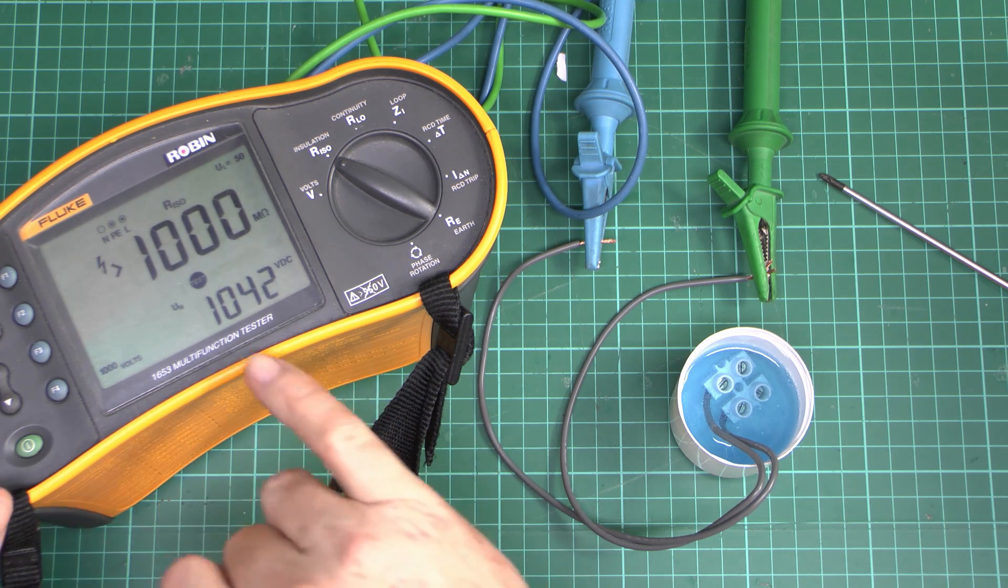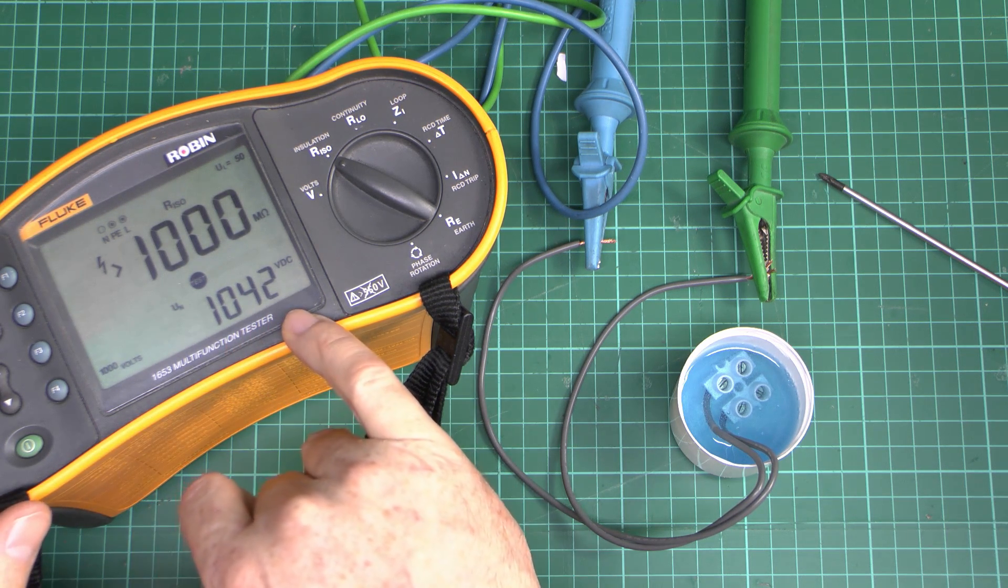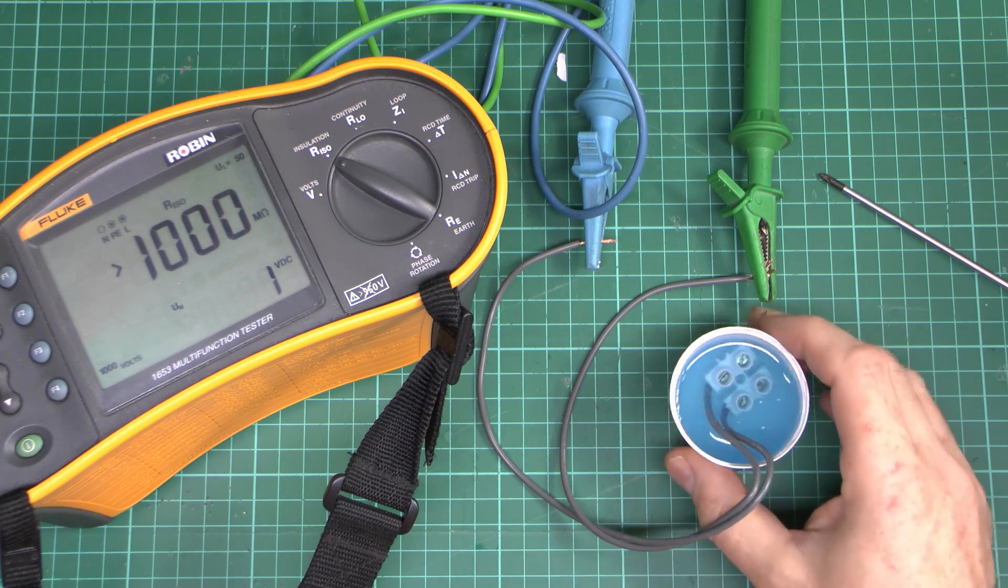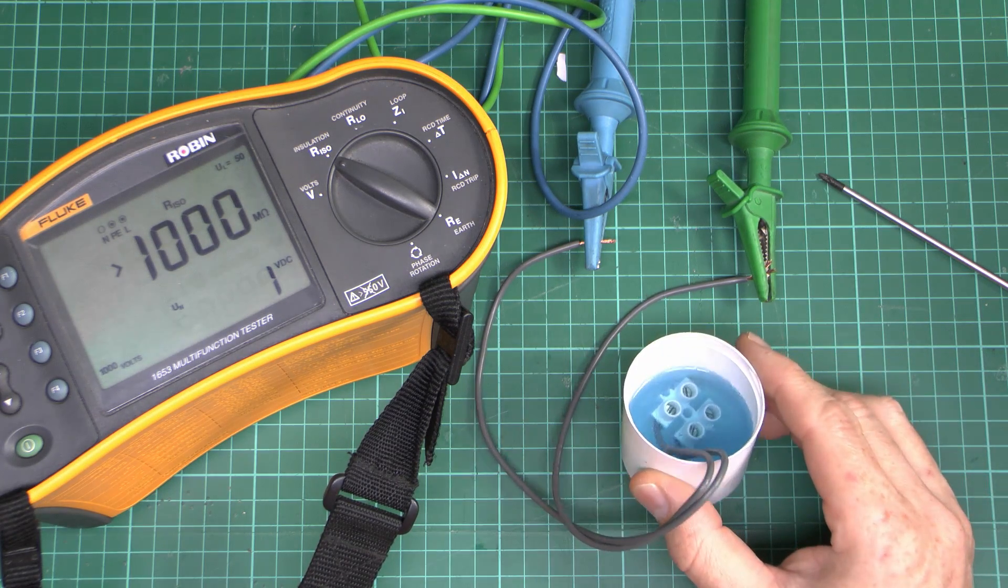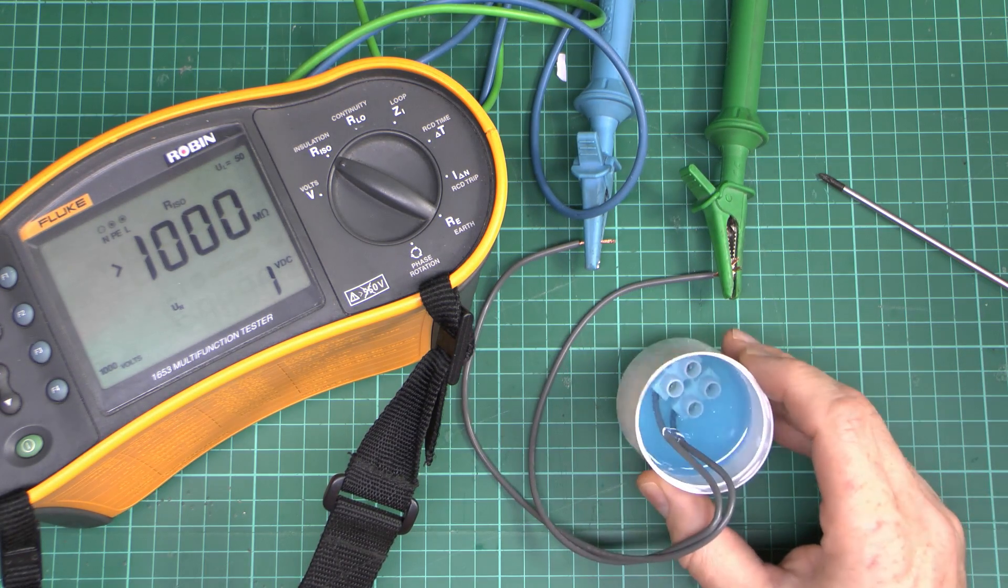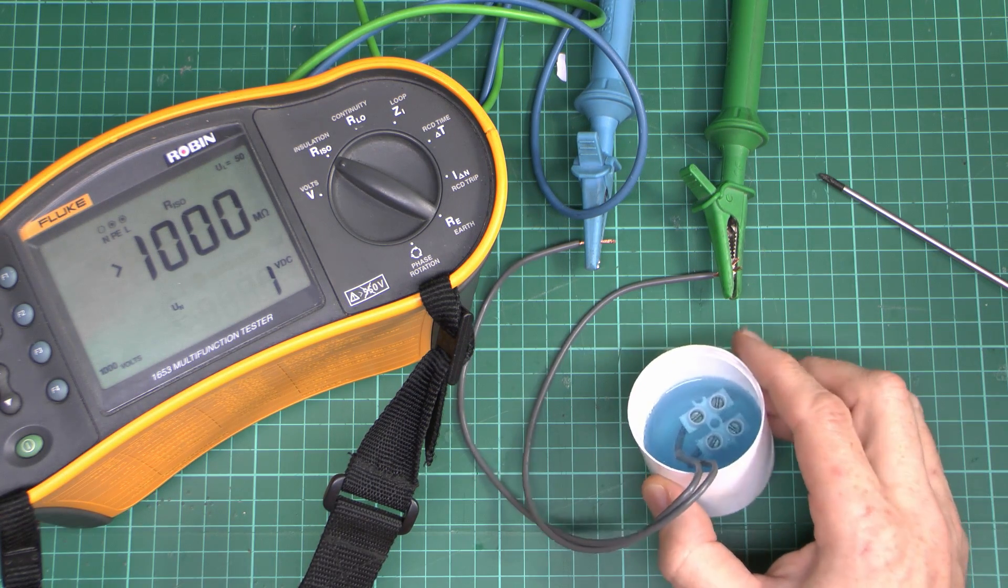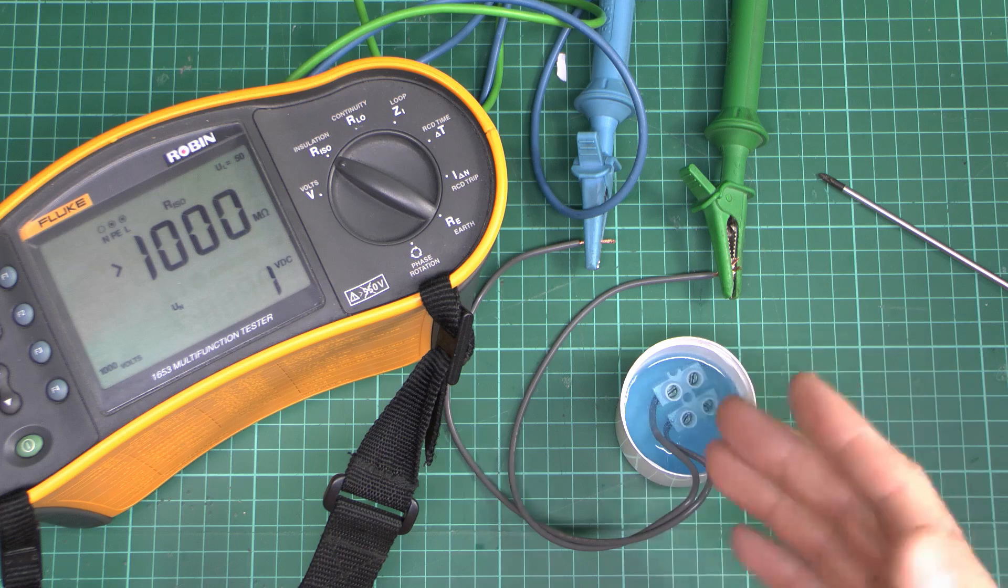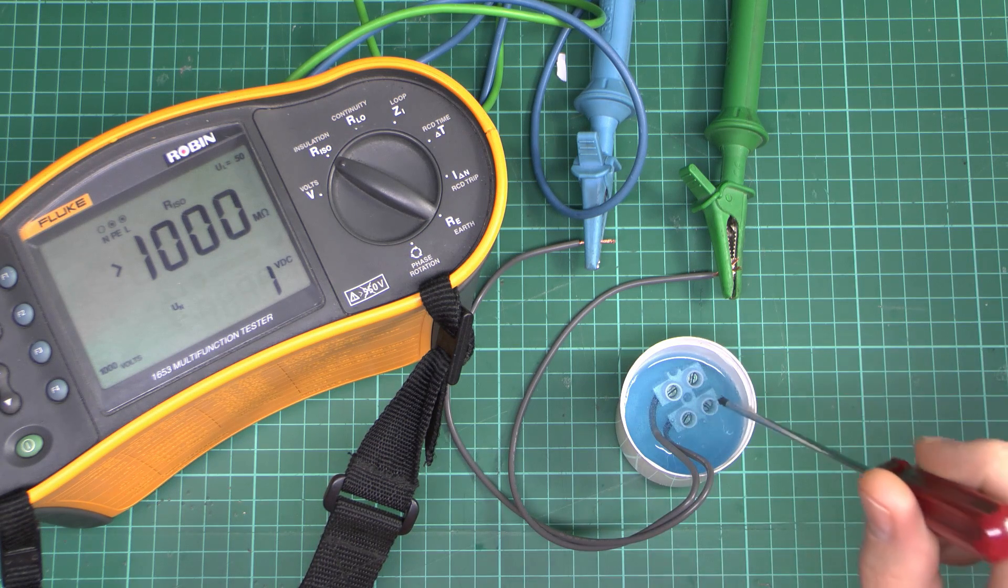So as you can see there, that's applying a test voltage of 1042 volts. And the resistance we're getting is greater than 1000 megaohms, basically more than one gigaohm. And that's despite it being in this what appeared to be a liquidy thing before, but of course there's no water involved there. And it's a completely insulating material.